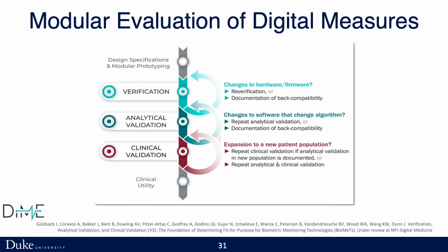And so if you're using a Fitbit version 2 and you haven't changed the hardware and everybody in your study is using the same version of the device, but actually the company pushes a software update that changes the way a heartbeat is detected from PPG, for example, and if you're not aware of that change in the firmware, then actually your data can change at a certain point in the study without you knowing.